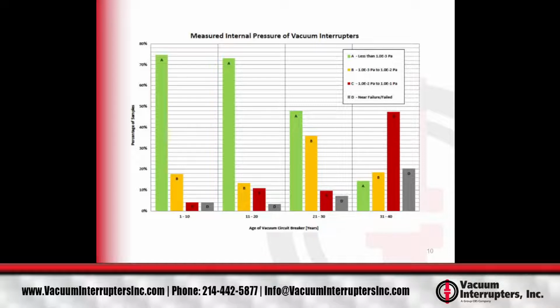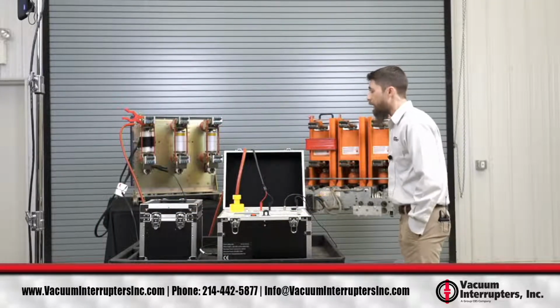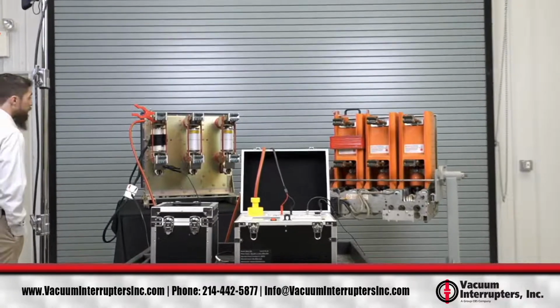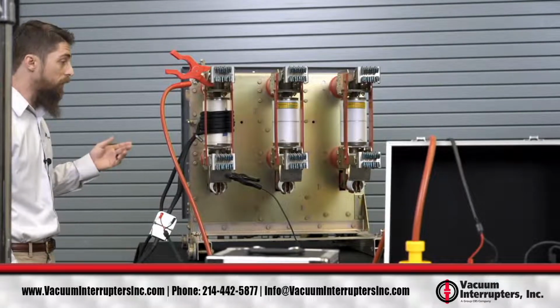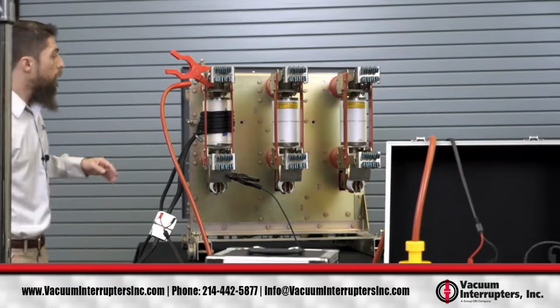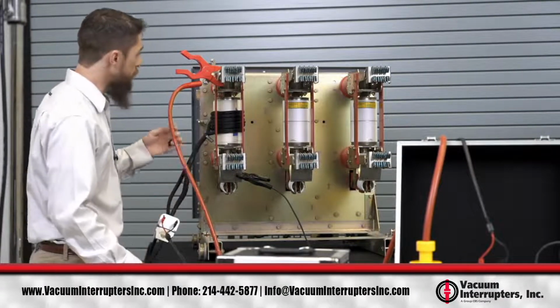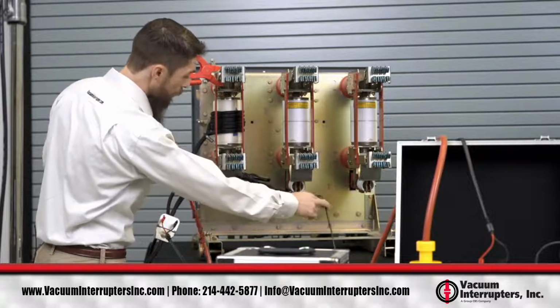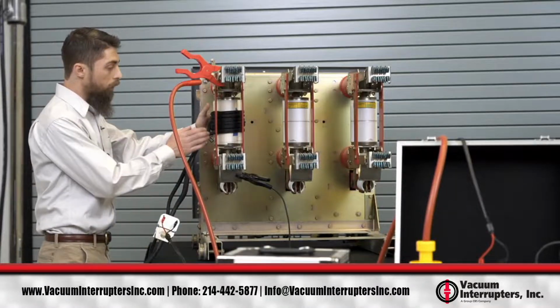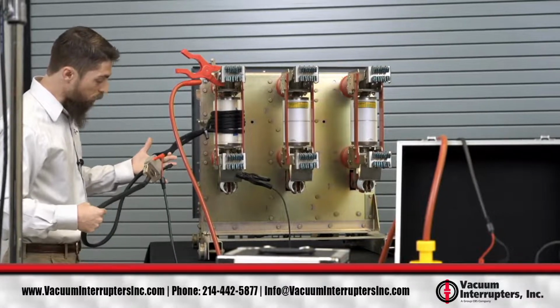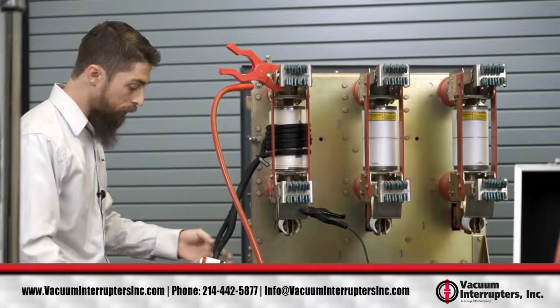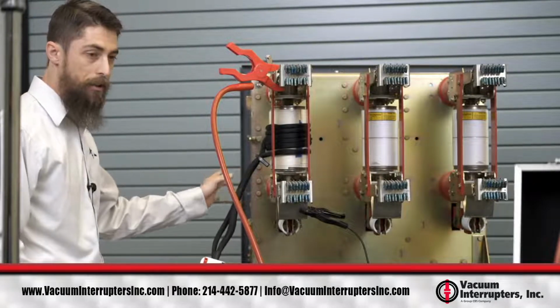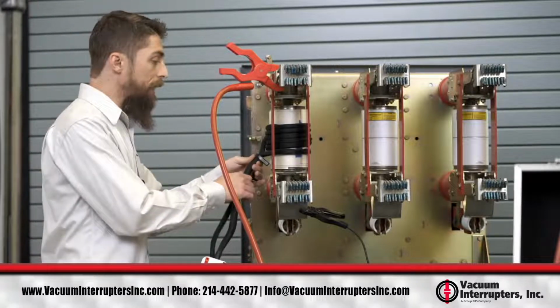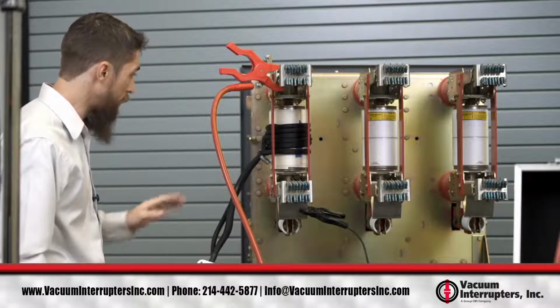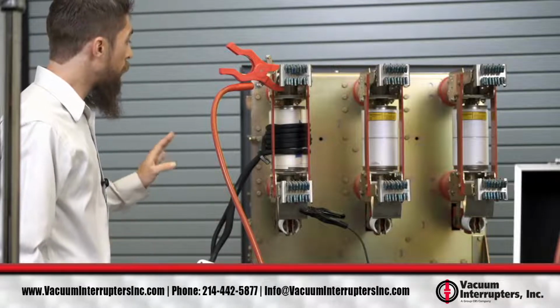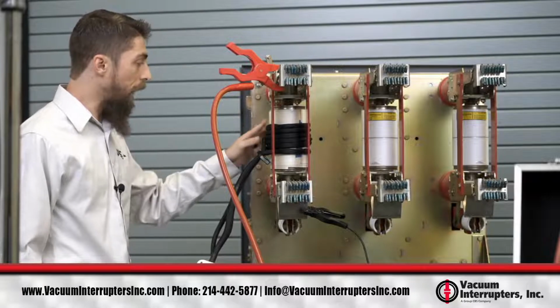Now I'm going to go to a live demonstration of our MAC set. Here I've got a VCPW type breaker. This breaker was originally made by Westinghouse, then Cutler Hammer, and now Eaton. To perform the test, we have our high voltage connections: red high voltage, black signal return. And then we have what we call the universal flex coil. This is the way that we're able to provide the magnetic field to the vacuum interrupter. This is generic; it goes with every MAC tester. If you can test with the flexible coil, then that's probably the best way to do it. For the coil, you want to wrap it at least 5 times around the vacuum interrupter.